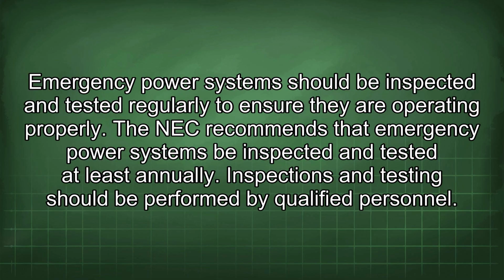Emergency power systems should be inspected and tested regularly to ensure they are operating properly. The NEC recommends that emergency power systems be inspected and tested at least annually. Inspections and testing should be performed by qualified personnel.